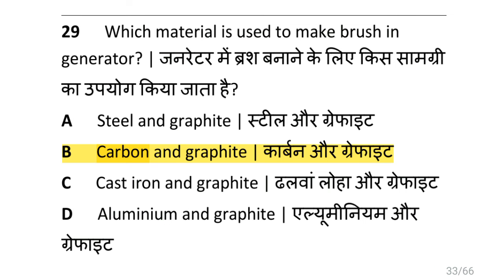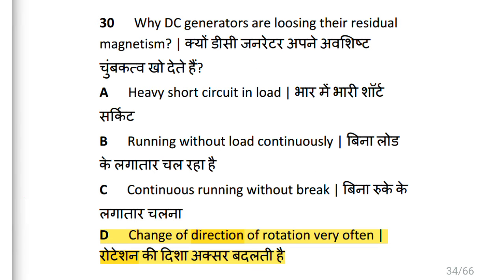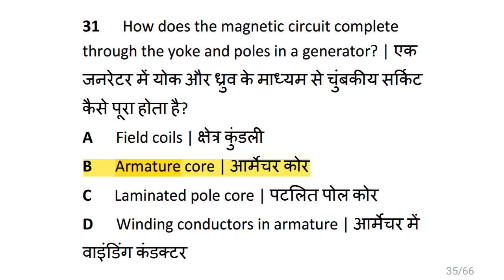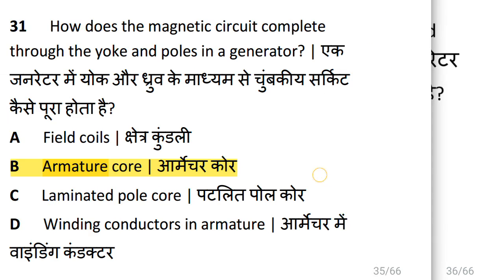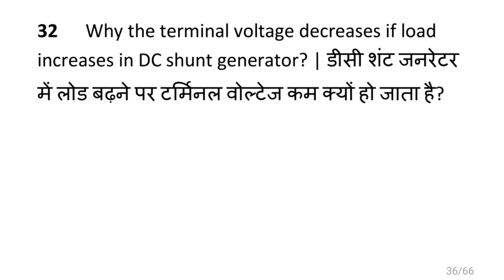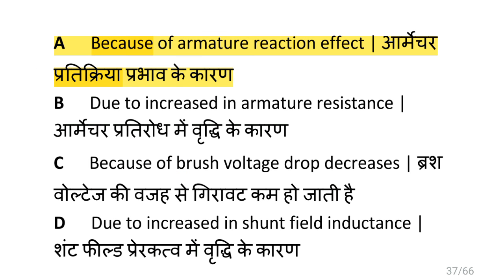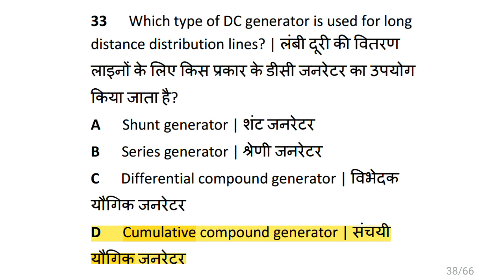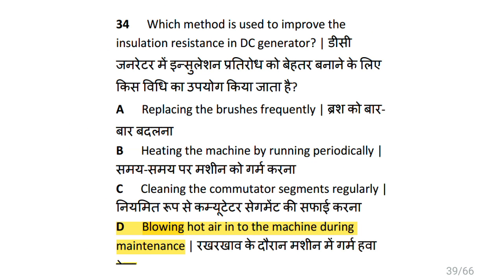Which material is used to make brushes in a generator? That is carbon and graphite. Why do DC generators lose their residual magnetism? Because of changing the direction of rotation very often. How does the magnetic circuit complete through the yoke and poles in a generator? That is by armature core. Why does terminal voltage decrease when load increases in a DC shunt generator? That is because of armature reaction effect. Which type of DC generator is used for long distance distribution lines? That is cumulative compound generator. Which method is used to improve insulation resistance in DC generator? That is blowing hot air into the machine during maintenance.